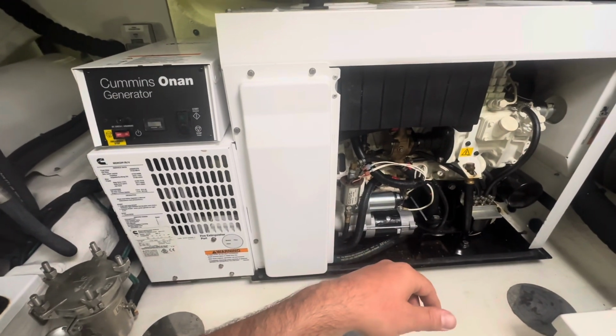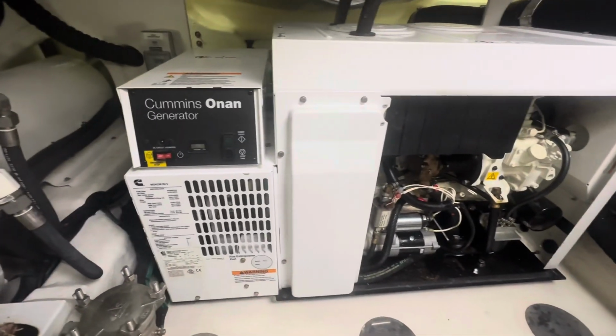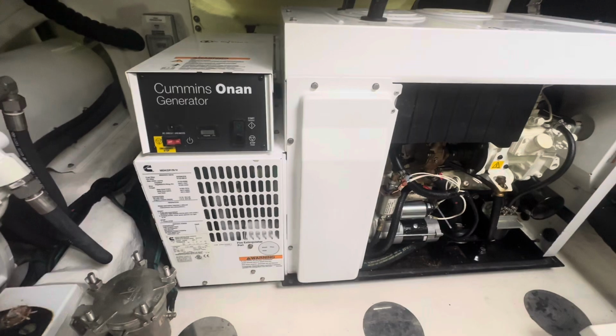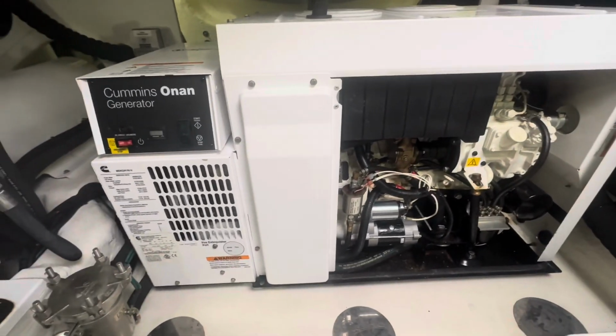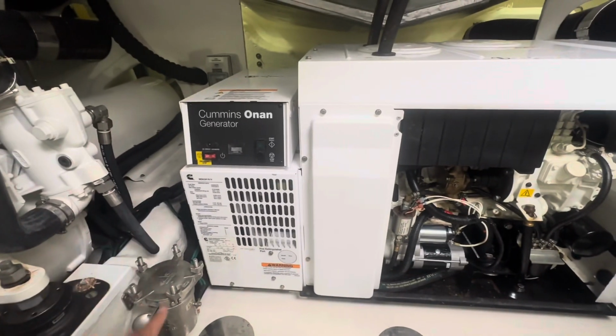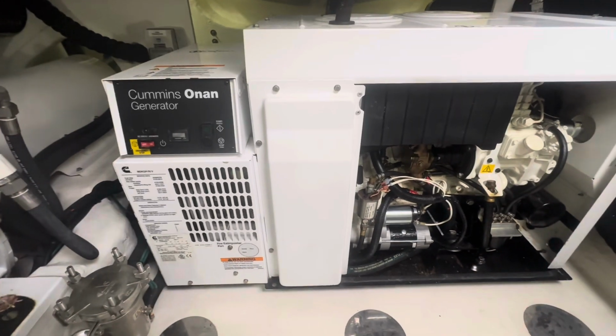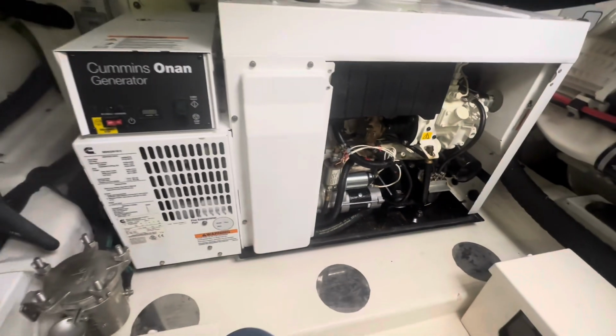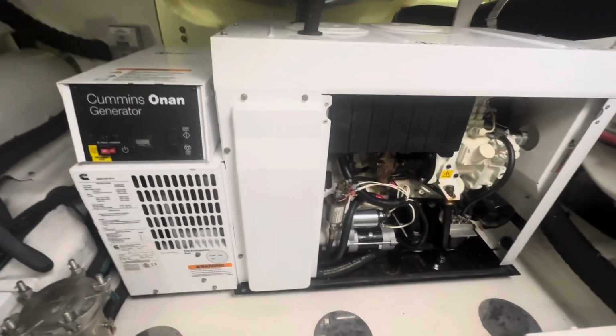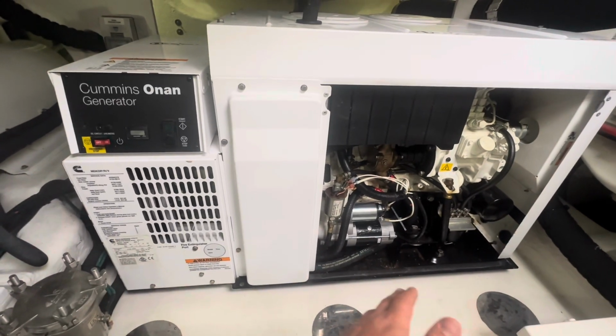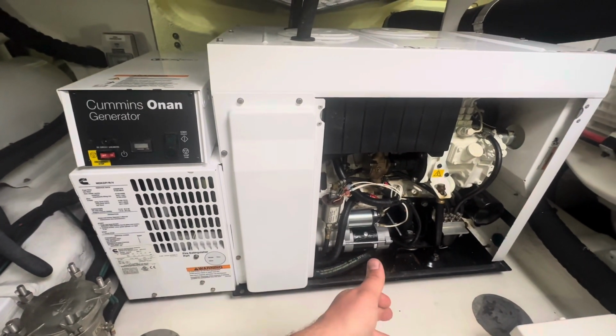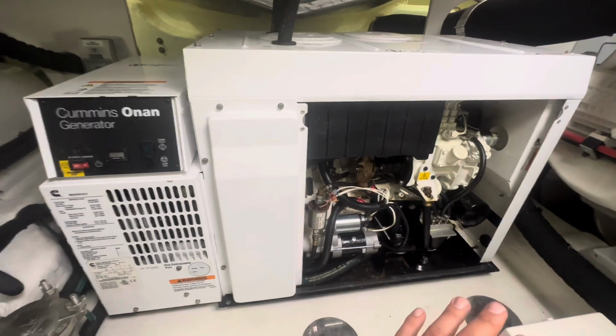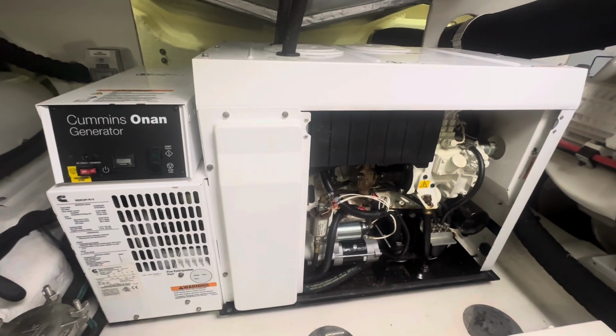Very strange. So I turned the battery chargers off last week, got my voltmeter out, and started diagnosing the issue. With chargers off, I went over to the auxiliary bank and checked those with the voltmeter - they were at a standing charge of about 25 and a half, 26 volts. On a 24 volt system, for resting batteries that's totally fine.